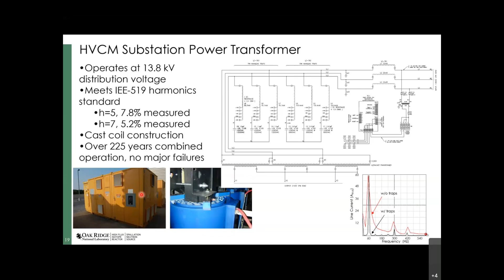It is a cast resin construction. There's no oil, which is rather nice, and so it's very low maintenance. These have been extremely reliable for us. All combined, with all the systems and all the operational years, there's over 225 years of operations on these systems. The only real failures we've had are the fan controller unit's temperature display, as the touchscreen has faded because of UV exposure, which one might expect from sitting out in the south-facing sun all day long.